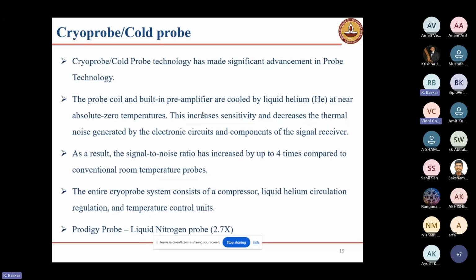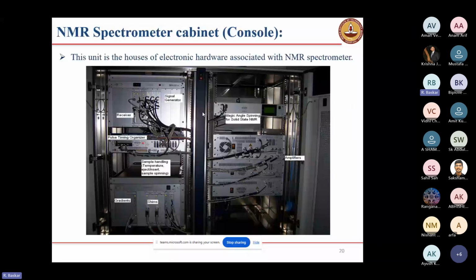And the next one is the Prodigy probe. Nowadays they have developed it. Its maintenance is a little cheaper compared to the cryo probe, but still expensive. Instead of liquid helium, they use liquid nitrogen. It will increase the sensitivity, signal intensity, 2.7 times. That is the Prodigy probe. So now I have completed the NMR magnet part and probe part.